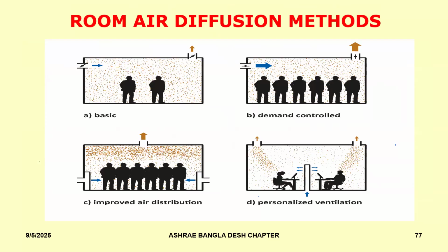To summarize all that we learned, this is your basic mixing air system where the air comes from the top and is exhausted out. So what is happening is all the pollutants, everything is getting mixed up in the room. We can control the amount of outdoor air by bringing in demand control ventilation, where we bring in the right amount of outdoor air based on occupancy levels. Then we improve that system by using something like stratified systems or displacement, where the air is brought in from here. So they get to breathe the cleanest air instead of the fully mixed polluted air. And then we went one better with personalized ventilation systems like this, which helps us make sure that, using room air distribution, different methods, we are able to arrive at different methods of optimizing our air quality.